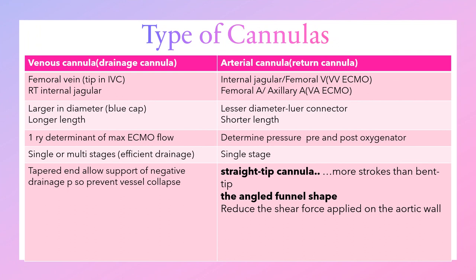ECMO circuits have two types of cannulas. The first is the venous cannula, or drainage cannula, which is usually inserted on the venous side regardless of the type of ECMO — veno-venous or veno-arterial. It is inserted in the femoral vein or right internal jugular vein. These cannulas are larger in diameter and longer in length, and they determine the maximum ECMO flow. They can be single-stage or multi-stage, meaning they have multiple pores for efficient drainage, and their ends are tapered to support negative drainage pressure and prevent vessel collapse.